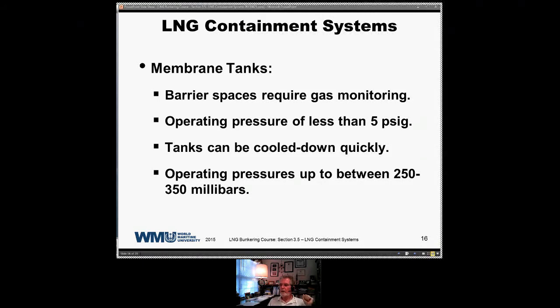When you're dealing with the spherical tank, you're talking a large amount of mass that has to be cooled down. One of the disadvantages of the spherical tank is that it takes a considerable length of time to do a cool down of one of these tanks because of the mass involved. You're looking at a thickness of probably about 2.5 inches, 50 plus millimeters at the bottom, up to 8 inches at the equator, and 1.5 inches at the top. So you've got all of this mass that has to be cooled down prior to the introduction of liquid into the tanks. So cool down for a spherical tank could take upwards of 40 hours, 48 hours, something in that area. You can cool down a membrane ship in about 8 to 12 hours. I think the difference is the time required and the quantity of product required to cool down.